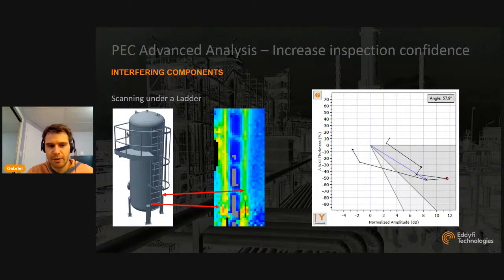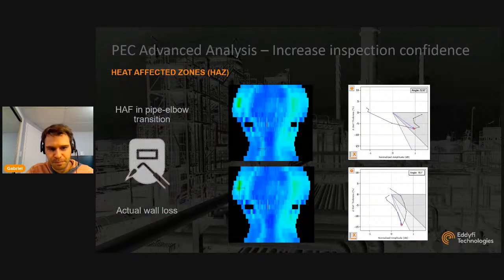So we've got a pressure vessel here. The technician scanned in between the pressure vessel and the ladder. They thought that there was wall loss in that region, but actually what we were seeing is the interference from the ladder on the PEC signals. So when you apply the PERM tool to, say, this area here that looks like a localized area of more significant corrosion, you're seeing that the PERM tool is pointing into that gray zone. That's a false positive. And you can see here actually the shape of the ladder. So, you know, you've got visual cues within the C-scan. Using the context, you can understand that there's something going on. But the PERM tool is going to confirm to you that this is indeed a false positive.